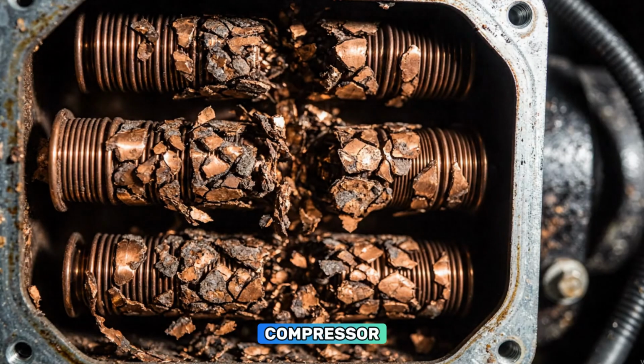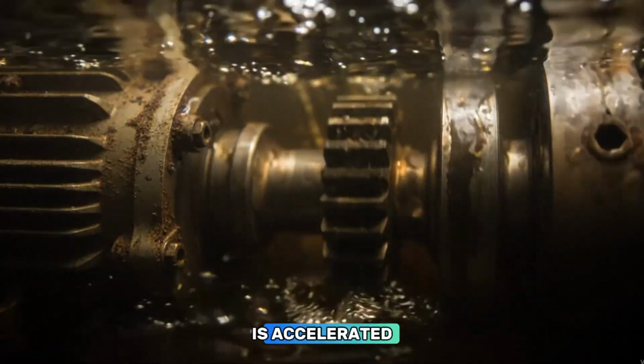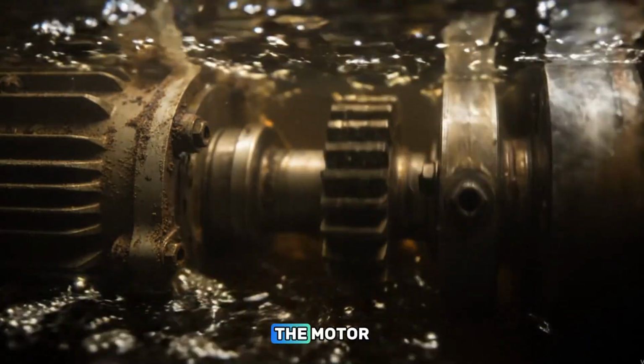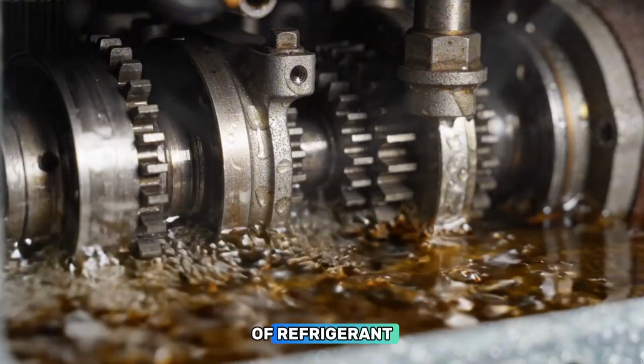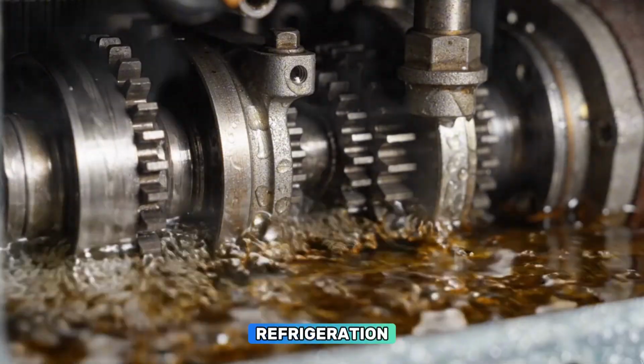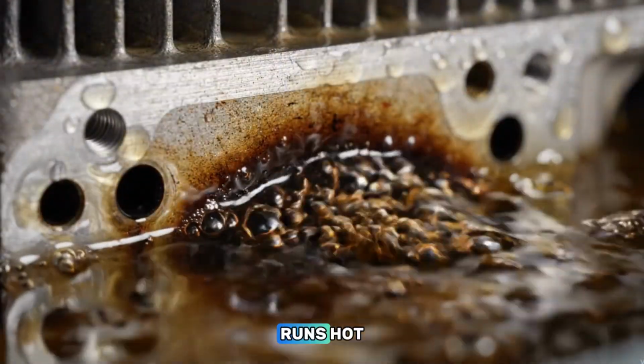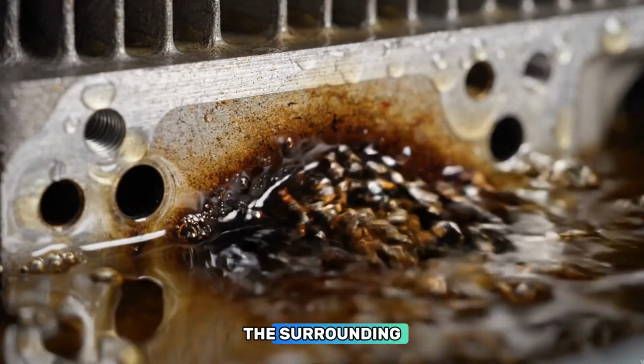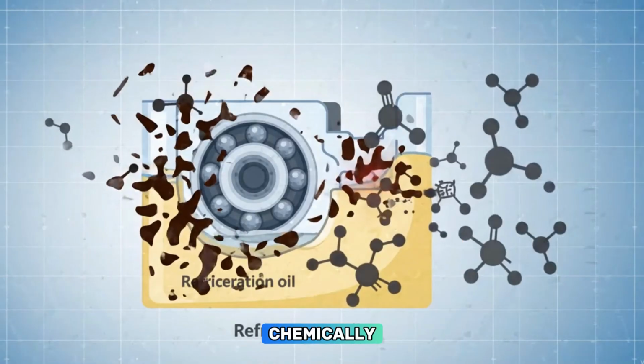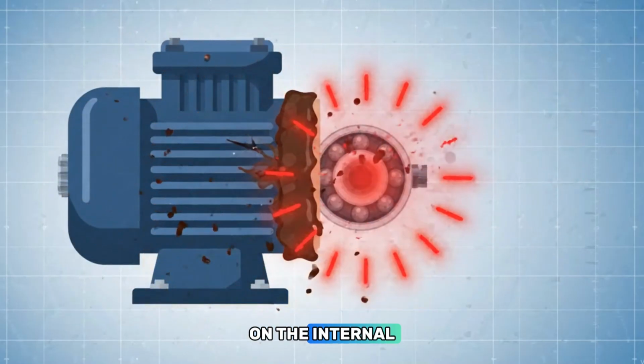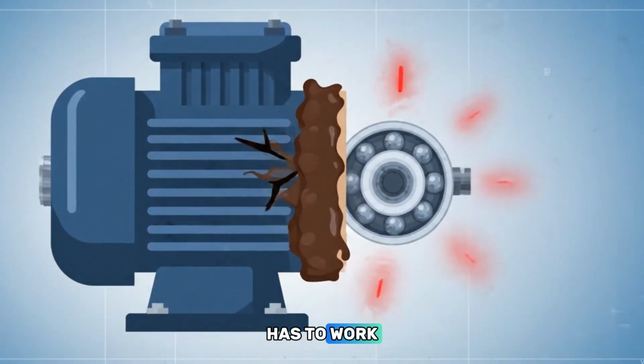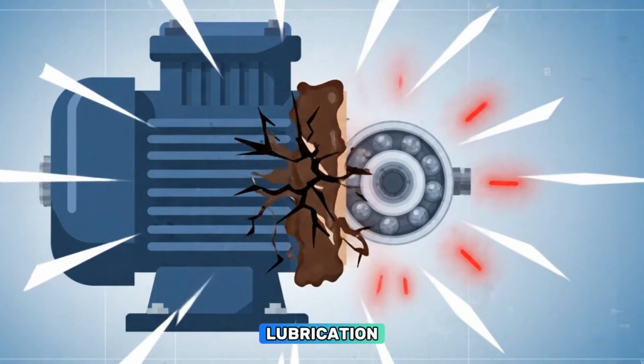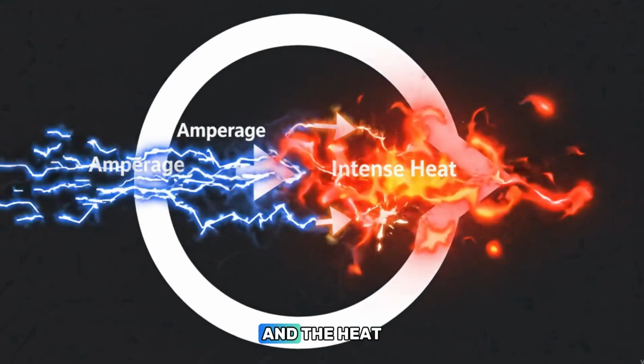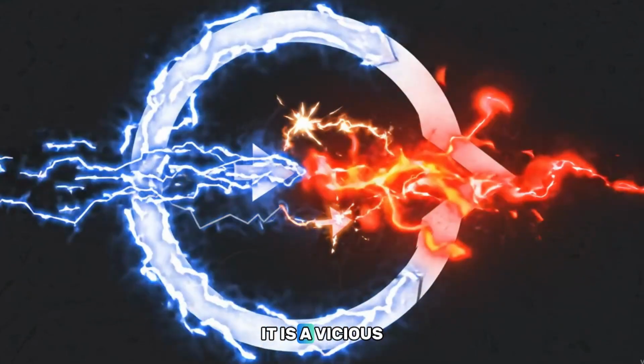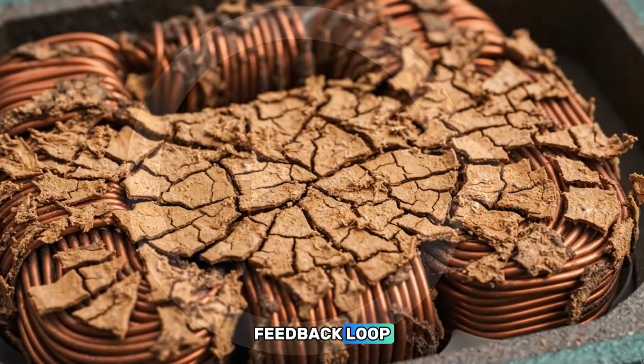Inside an HVAC compressor, this degradation is accelerated by the environment. The motor operates submerged in a bath of refrigerant gas and specialized refrigeration oil. As the motor runs hot, it scorches the surrounding oil. The oil breaks down chemically, increasing the friction on the internal bearings. The motor now has to work even harder to overcome the degraded lubrication, driving the amperage and the heat even higher. It is a vicious, inescapable feedback loop.